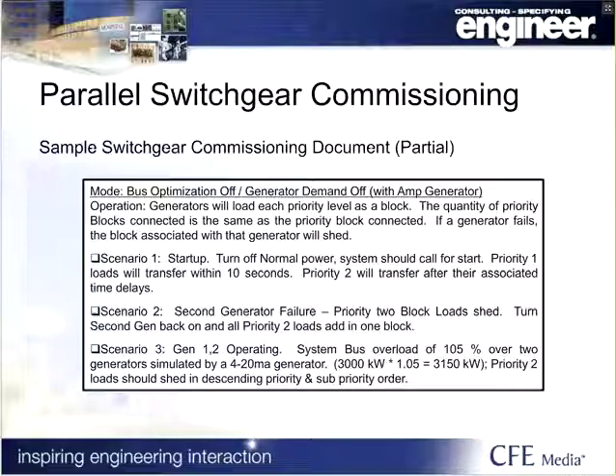So in this situation, I just cut out a snippet of a commissioning document that I've used in order to check the performance of the system. Like scenario 1, basically I just killed power to the normal, make sure that the priority 1 loads come on in 10 seconds, and boom. So they're good. We checked that. Then I've got 2 generators running. I'm going to kill the 2nd generator, and let's just pretend it failed. What happens to the system?